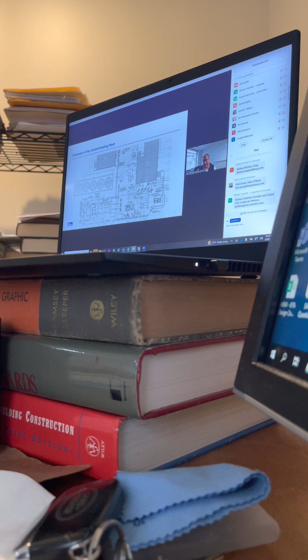Our contracts require that we pay for the natural gas whether we use it or not over the entire year. So we have a situation where we basically run our boilers 365 days a year. They sometimes power the steam chillers, but they also send steam and hot water to various facilities where that is used to temper the chilled air that's generated by the fan room. So this was set up for when energy was very inexpensive and readily available. During the summer we basically have the chillers battling the boilers. So it's a great system, works really well, but has some efficiency limitations. So next slide.